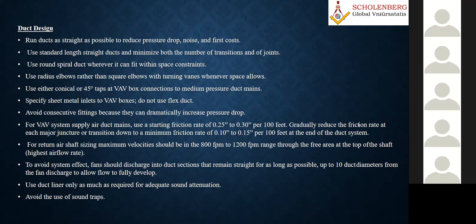And I have also shown some of the design parameters earlier, the ducting, how we have to take the elbows and joints in the drawing. But because when you do many things during the design, you don't anticipate the site considerations. So whatever you do, even the working drawings, after that, working drawings are coming to you and you approve it. But at a later stage, during the execution time, when this is going to be installed, the project engineers or the air conditioning resident engineer will face thousands of problems. And as per the site condition, they have to do some changes. But many times they don't inform. And then at a later stage, it becomes a serious problem during the testing and commissioning time.